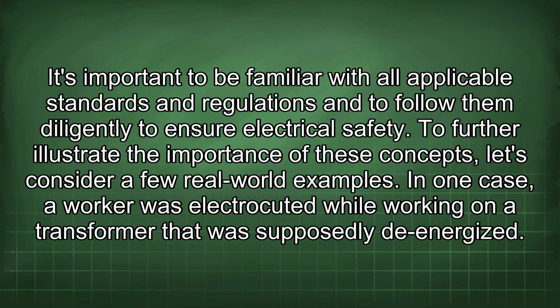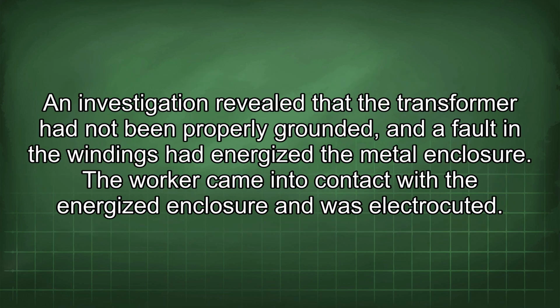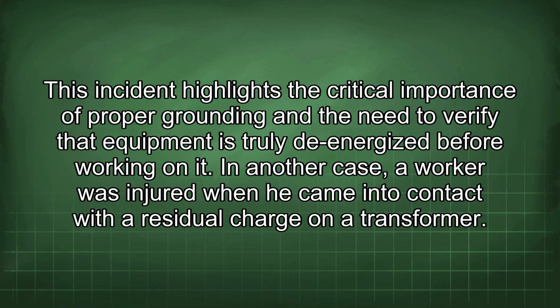In one case, a worker was electrocuted while working on a transformer that was supposedly de-energized. An investigation revealed that the transformer had not been properly grounded, and a fault in the windings had energized the metal enclosure. The worker came into contact with the energized enclosure and was electrocuted. This incident highlights the critical importance of proper grounding and the need to verify that equipment is truly de-energized before working on it.